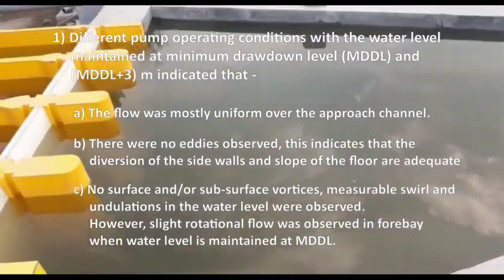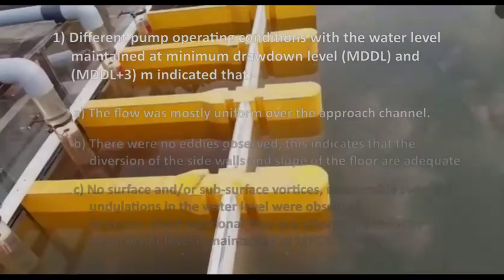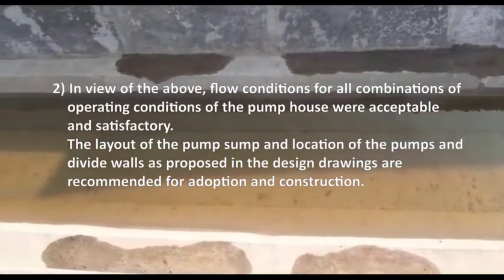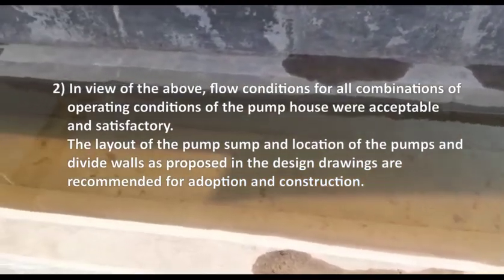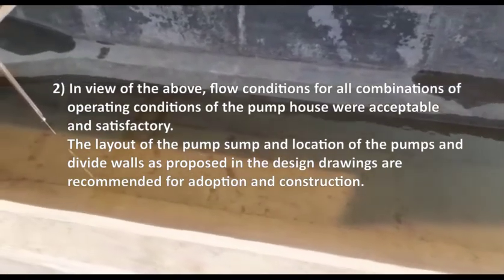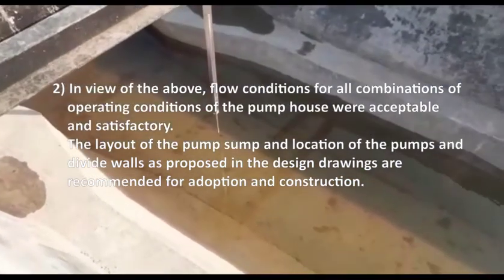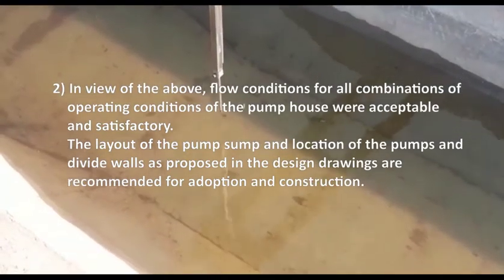However, slight rotational flow was observed in the forebay when the water level is maintained at MDDL. In view of the above, flow conditions for all combinations of operating conditions of the pump house were acceptable and satisfactory. The layout of the pump sump, and location of the pumps and divide walls as proposed in the design drawings are recommended for adoption and construction.